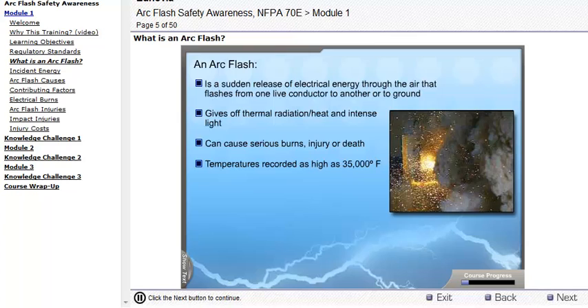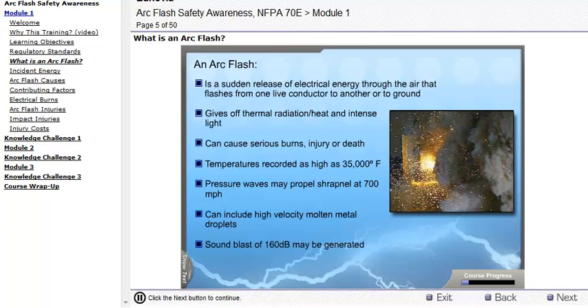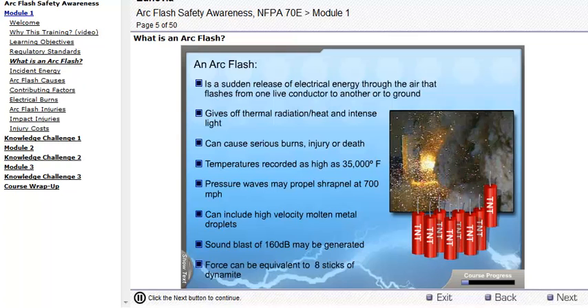An arc flash can even produce considerable pressure waves by rapidly heating the air and creating a blast. This pressure burst can hit a worker with such a force, as well as melt copper or aluminum electrical components, and send these metal droplets great distances at extremely high velocities. This is like 8 sticks of dynamite.